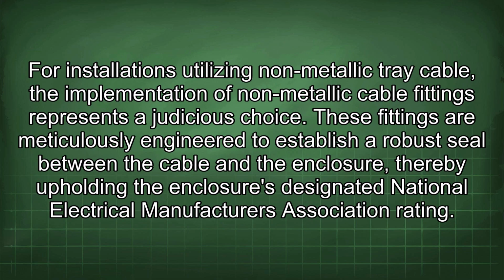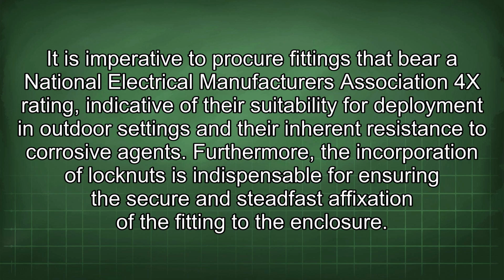For installations utilizing non-metallic tray cable, the implementation of non-metallic cable fittings represents a judicious choice. These fittings are meticulously engineered to establish a robust seal between the cable and the enclosure, thereby upholding the enclosure's designated National Electrical Manufacturers Association rating. It is imperative to procure fittings that bear a National Electrical Manufacturers Association 4X rating, indicative of their suitability for deployment in outdoor settings and their inherent resistance to corrosive agents.